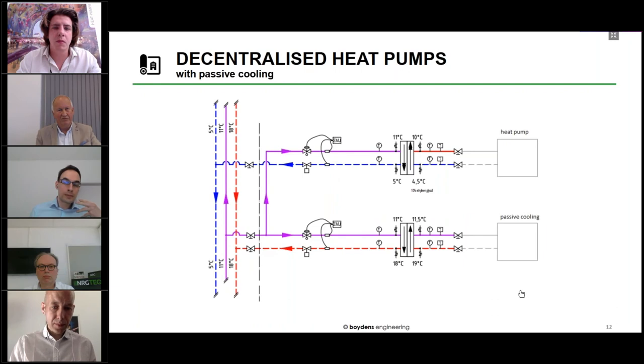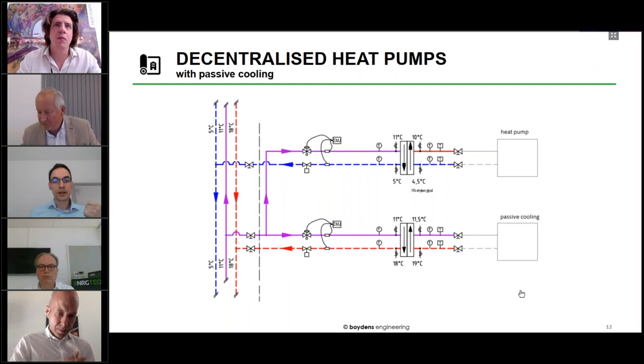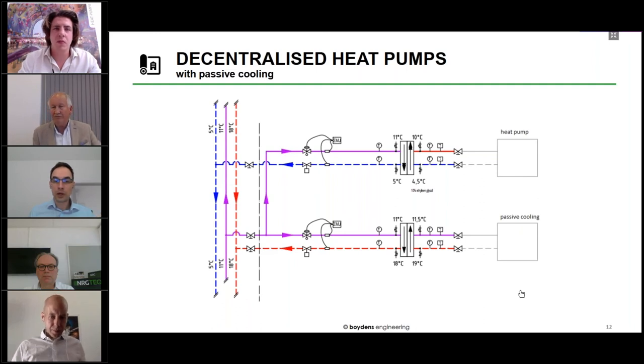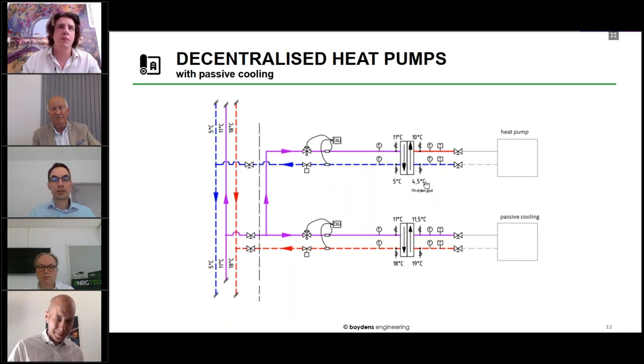So, now, maybe still to explain something more about the decentralized heat pumps that are used here, there can be two types that can be used. The first one is with passive cooling, as can be seen in this example. What we have here is the middle pipe at 11 degrees Celsius in magenta color. It can either be distributed towards a local heat exchanger and then directly used for cooling of a building on the secondary side, or it can be used on the other heat exchanger, and there is a heat pump on the secondary side.